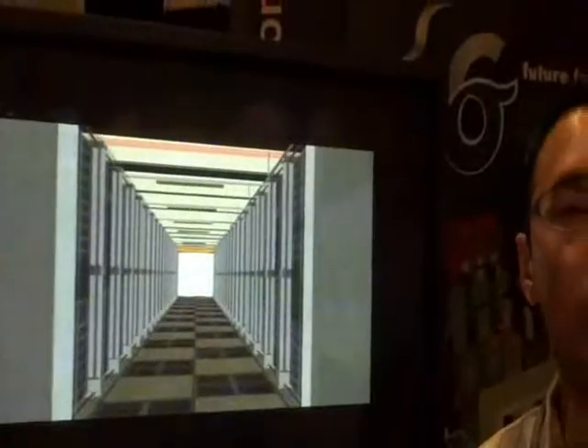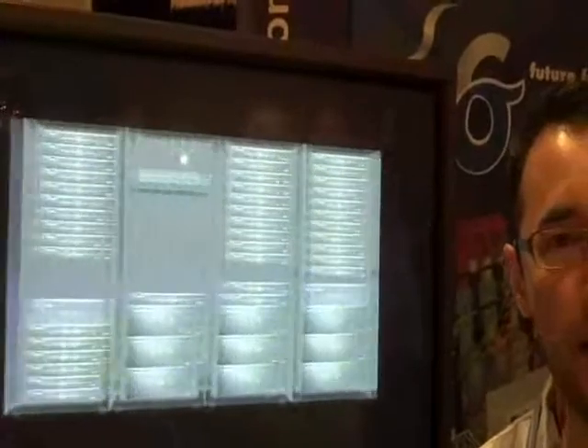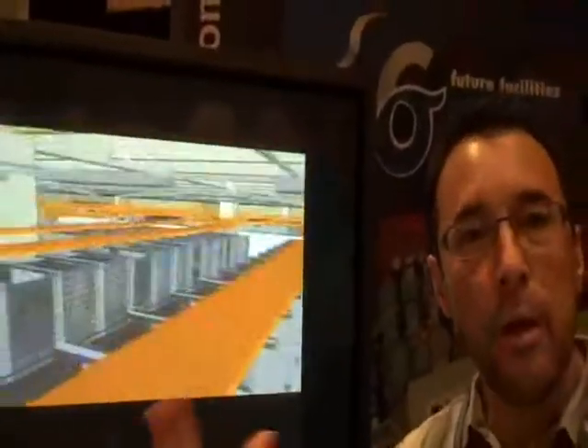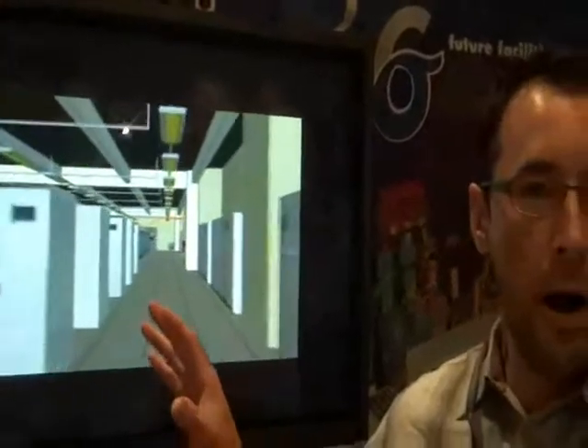As you can see, these types of models for operational live data centers are very detailed. It's got a complete description of the IT infrastructure, including a complete listing of IT equipment, and where they sit in the room and in the cabinets. On the infrastructure side, it models the cooling system in a lot of detail, including how they're controlled. In this case, this is controlled on return air temperature. This level of resolution is necessary in order to manage properly space, power, cooling, and air flow.